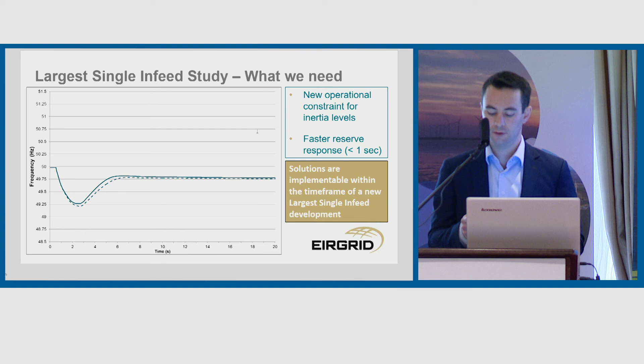At the moment we've defined a 2-second fast frequency response service that gives us a response up to 2 seconds after an event occurs. If we want to go beyond 500 megawatts, we need to decrease this down to 1 second, which means new technologies connecting to the grid to help manage this type of in-feed. Given the connection timelines, we believe we can implement this within the timeframe of a new largest single in-feed.